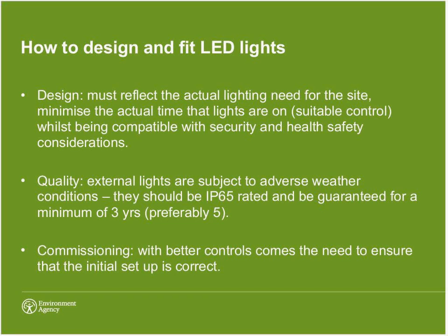And what we've done is that areas of the site which are largely unoccupied out of hours will be lowly lit. When the incident response team come on site, their way is lit towards the access to the building. So the lights are at a very low lux level, and they will ramp up as people enter the site. So it's getting a good balance between saving energy, but also maintaining the quality of light that we need to maintain health and safety and security.